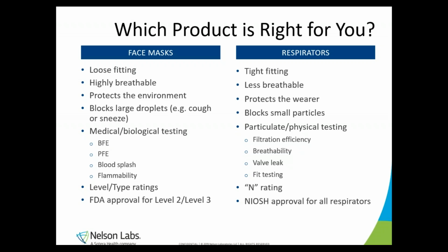Respirators are tight-fitting to the face, and they're less breathable than face masks. This makes it so that they can protect the wearer by blocking small and large particles. They're required to have more physical testing than the face masks, with filtration efficiency, breathability, valve leak testing if an exhalation valve is included, and fit testing to ensure that the tight-fitting respirator seals all the way around the face. Here in the US, they receive an N rating for particulate respirators, and NIOSH approval is required for all respirators.